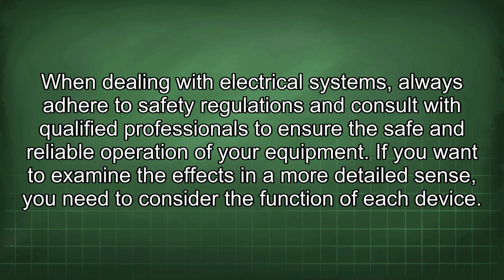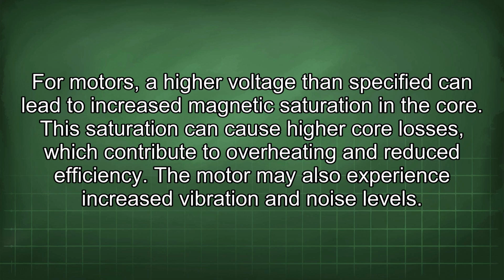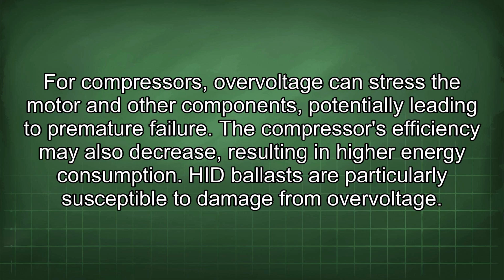If you want to examine the effects in a more detailed sense, you need to consider the function of each device. For motors, a higher voltage than specified can lead to increased magnetic saturation in the core. This saturation can cause higher core losses, which contribute to overheating and reduced efficiency. The motor may also experience increased vibration and noise levels. For compressors, overvoltage can stress the motor and other components, potentially leading to premature failure. The compressor's efficiency may also decrease, resulting in higher energy consumption.